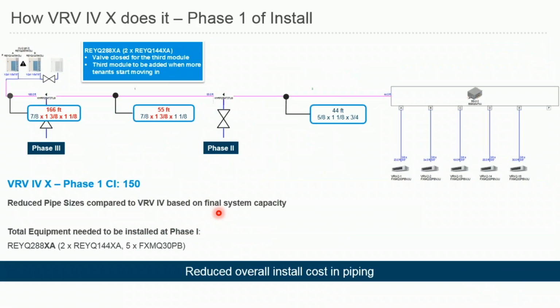So let's look at how VRV4X is doing this. Again, your final capacity will be the same. So eventually you'll be needing a REYQ432 model to provide the full capacity for the whole building. But again, this time you're following a different approach. For the first phase of the project, instead of installing 8 indoor units in total, with only 5 indoor units, you're able to get to the minimum connection ratio limitation.